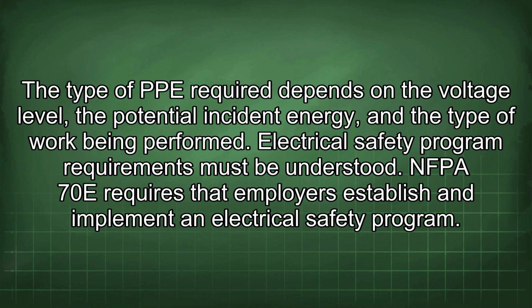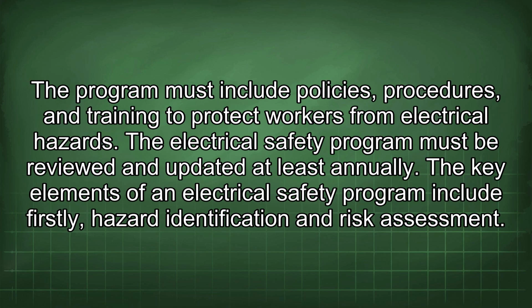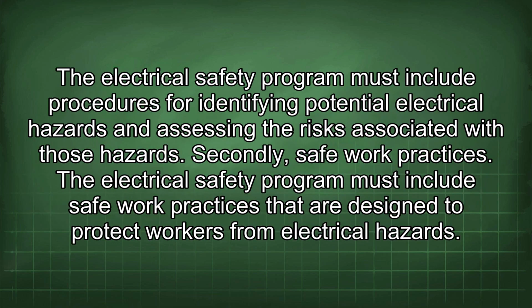NFPA 70E requires that employers establish and implement an electrical safety program. The program must include policies, procedures, and training to protect workers from electrical hazards. The electrical safety program must be reviewed and updated at least annually. The key elements of an electrical safety program include, firstly, hazard identification and risk assessment. The electrical safety program must include procedures for identifying potential electrical hazards and assessing the risks associated with those hazards.